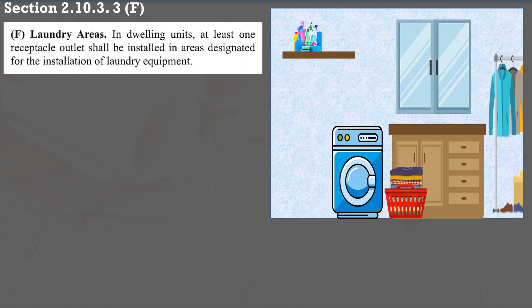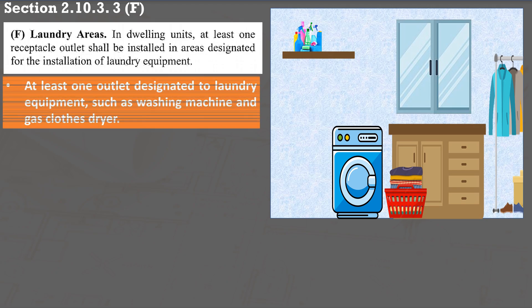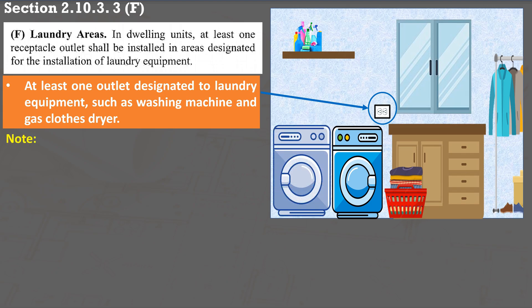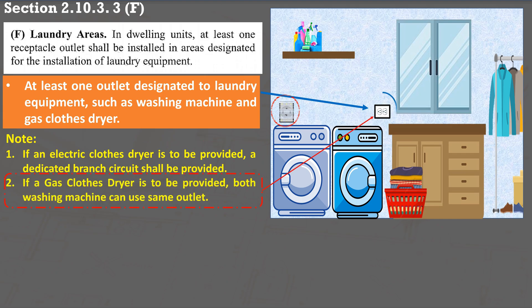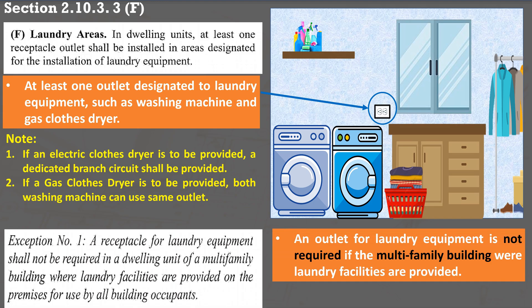For laundry areas as stated in section 2.10.3.3 F, at least one outlet is designated for laundry equipment such as a washing machine and gas clothes dryer. If an electric dryer will be provided, an additional outlet is required and it must be on a dedicated branch circuit. If a gas clothes dryer is provided, both the washing machine and gas dryer can be plugged into the same outlet. A receptacle outlet for laundry equipment is not required if a multi-family building provides laundry facilities on its premises for building occupants, as stated in exception 1.